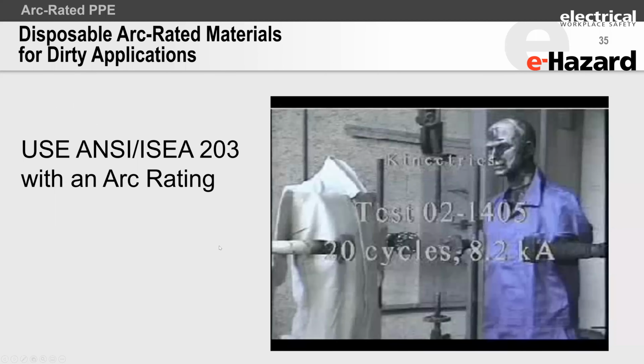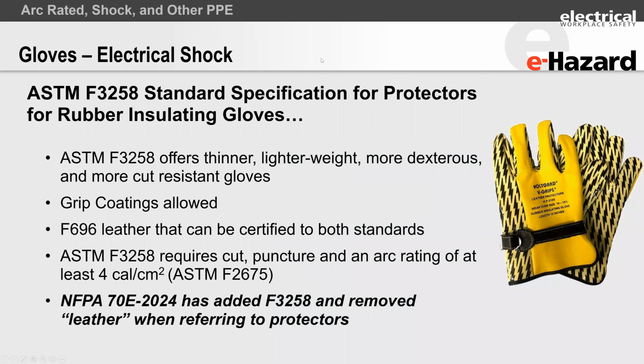I always recommend using ANSI ISEA 203 and getting an arc rating on that fabric. The fabrics are flash fire tested as part of 203. They have flame tests and all kinds of details in them, but get them with an arc rating, and they're excellent to use over top of gear if you have some minor chemical exposures. So just make sure you think about that and use those.